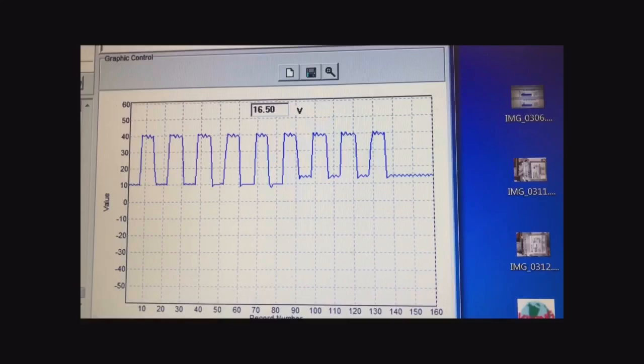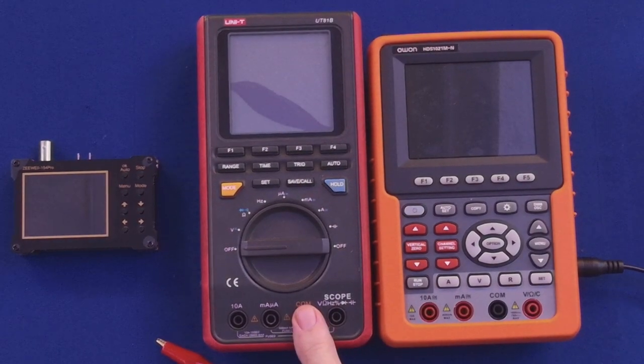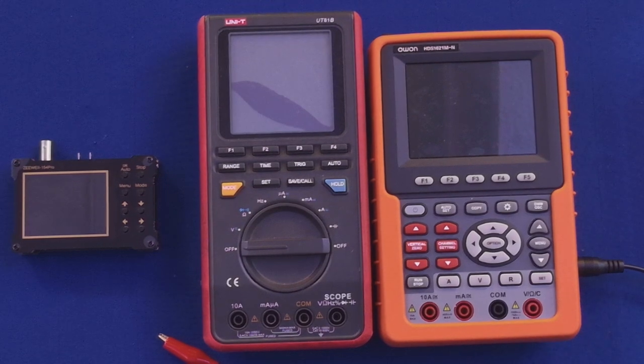it had an addressable relay on it. And lo and behold, that was what was doing it, that addressable relay. So once I removed and replaced that addressable relay, the problem stopped. Then I moved on. Since I had broken this one, I bought this one.